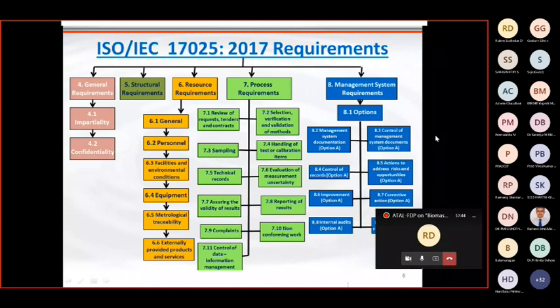Second, you have a lot of reference standards, reference samples, reference data. These are all used for testing or calibration. So how do you select, verify, and validate such reference standards, methods, and tools? If there are international, national, or published standards, it's easy to adopt by both the customer and the laboratory. In case it is not there, you will choose what is available in the market, or a customer-supplied one, or what you develop from your laboratory. But agreeing upon this is an essential requirement, so that is addressed here.